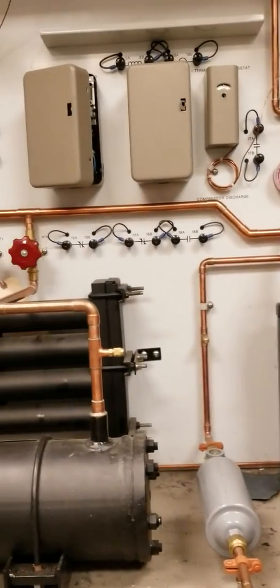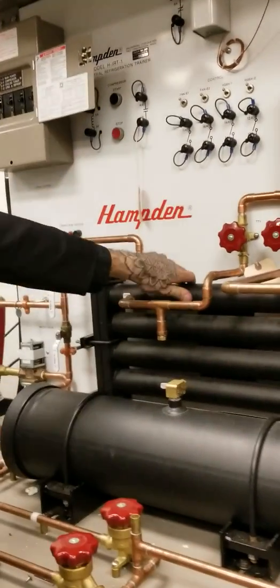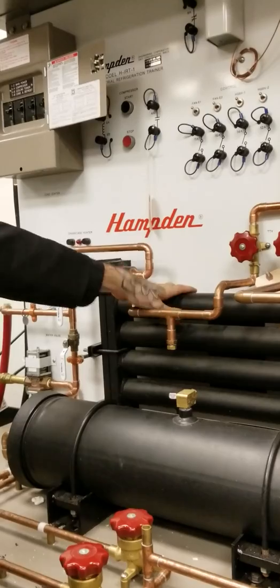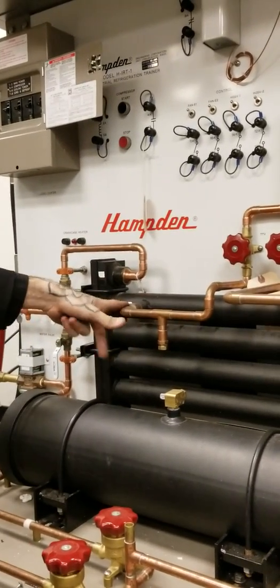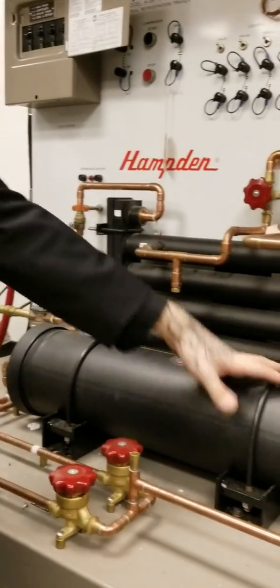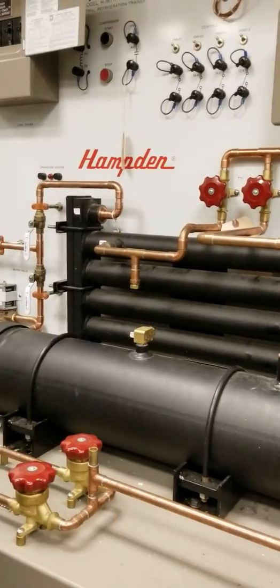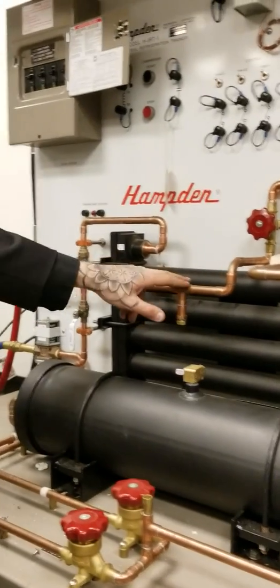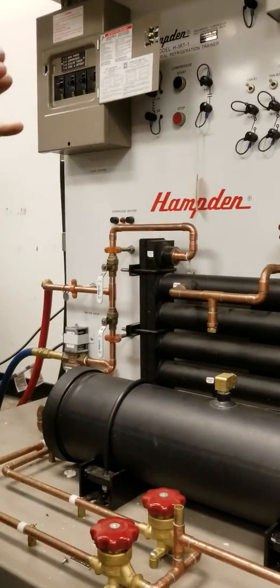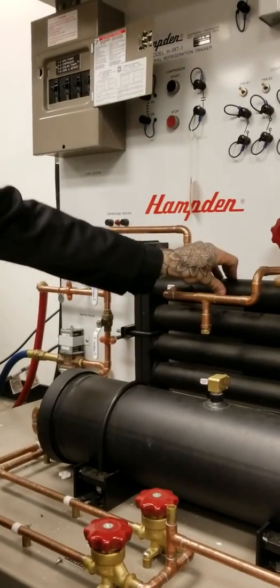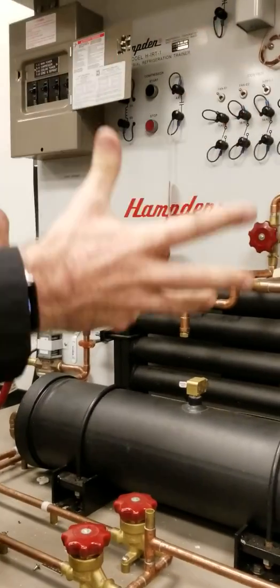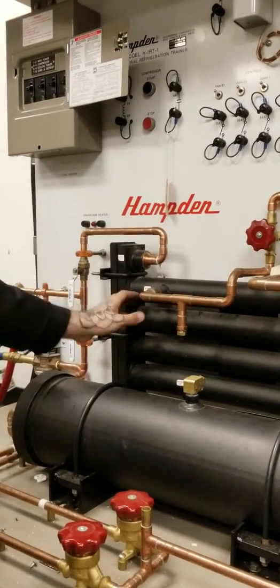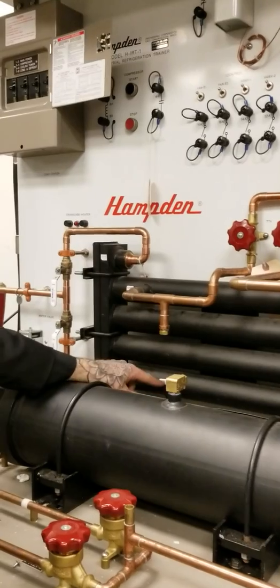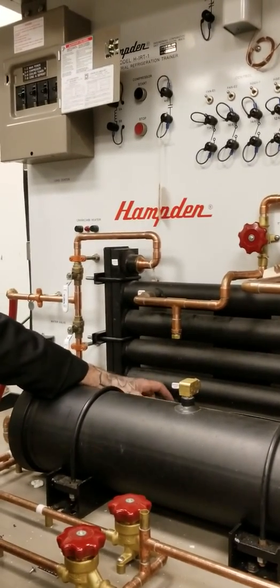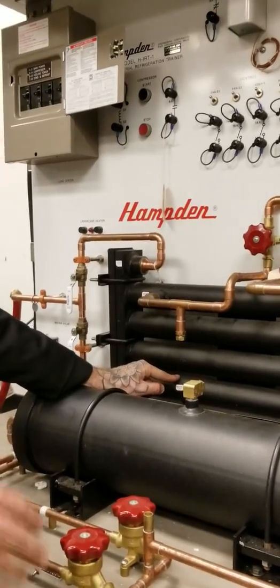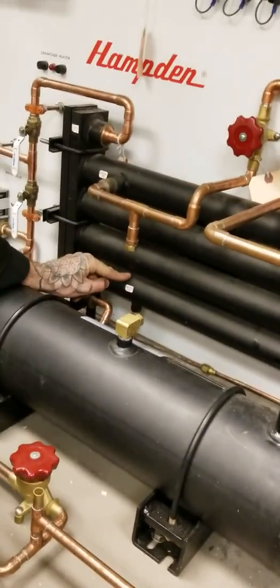Right here is just two different styles of condensers. You could either have a tube in a tube, which is one big design, where you'll have your refrigerant coming in through here, or you could have a shell and a tube, where your refrigerant will come in through the shell right here. And the way this is designed is you have this tube that's going to go into the cavity, or the space, inside this tube, right? It's going to go all the way around the tube, work its way through the bottom of these tubes and come out this refrigerant output. By the time the refrigerant leaves, we still want it to be subcooled, so it needs to reject enough heat until it drops below its saturation point and condenses.